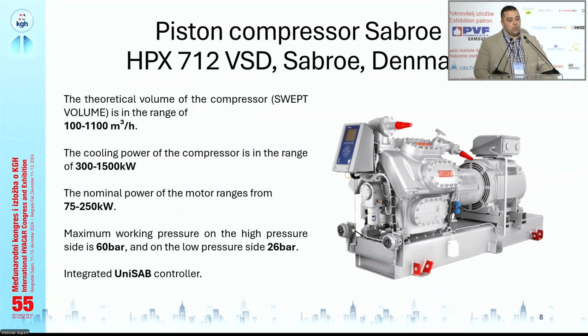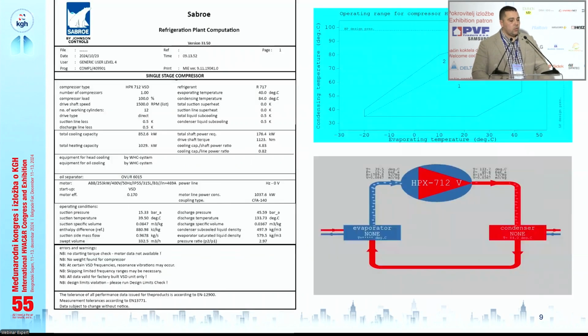Like most other Johnson Controls and Sabroe compressors, it has the Unisab controller, which is integrated into this package. Here we have just several details. On the left side is the data sheet from the matchmaker, which gives us more details about this particular application. We can see the evaporating and condensing temperatures and pressures. We can see the selected motor and some more details about the oil cooling.